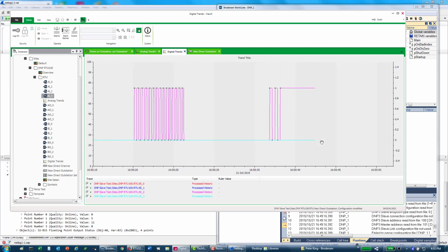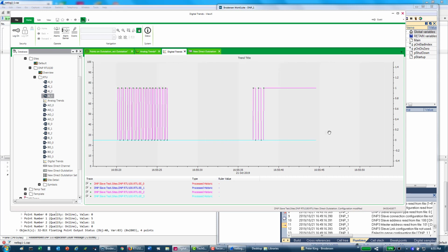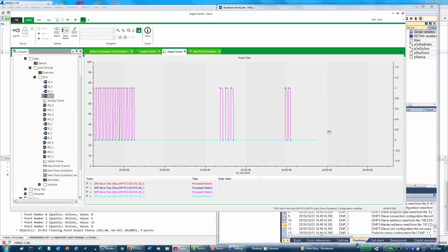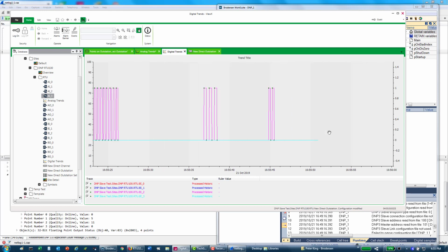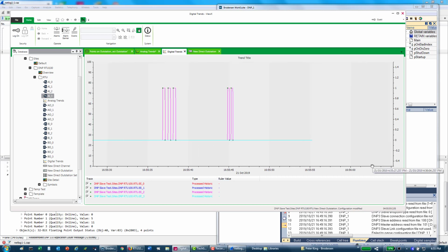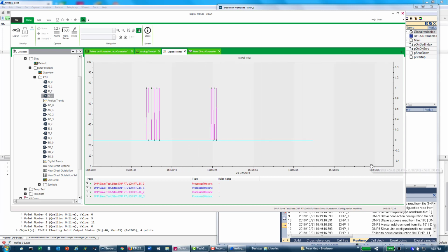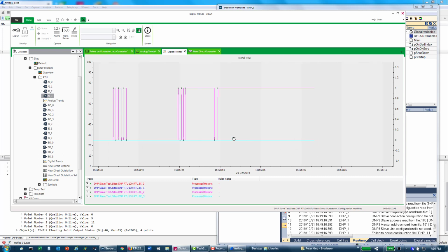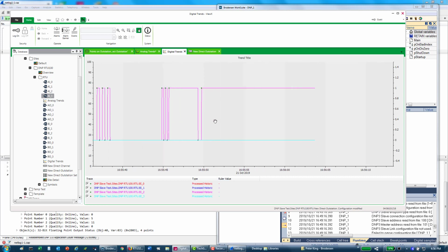So if I make 3 changes of state, that's 6 events. 1, 2, 3. So they get unsolicited. If I just go 1, 2, I haven't made enough, and we'll have to wait till we get to the point where the events are either 15 seconds old or the poll occurs. And the poll's occurred now, but it went back and got those events for me.